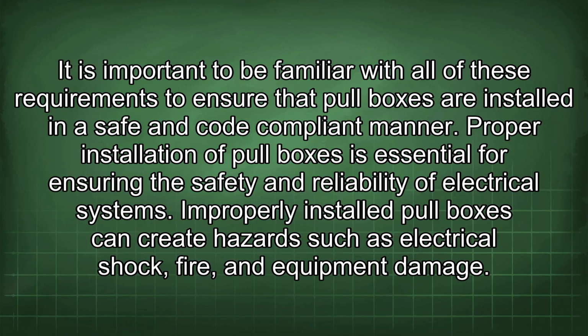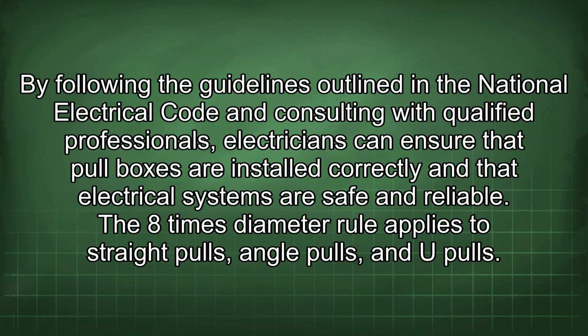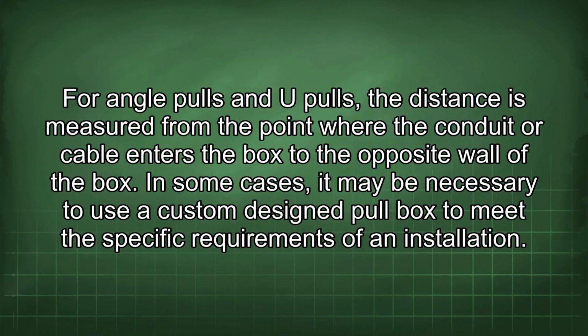Improperly installed pull boxes can create hazards such as electrical shock, fire, and equipment damage. By following the guidelines outlined in the National Electrical Code and consulting with qualified professionals, electricians can ensure that pull boxes are installed correctly and that electrical systems are safe and reliable. The 8 times diameter rule applies to straight pulls, angle pulls, and U-pulls. For angle pulls and U-pulls, the distance is measured from the point where the conduit or cable enters the box to the opposite wall of the box.